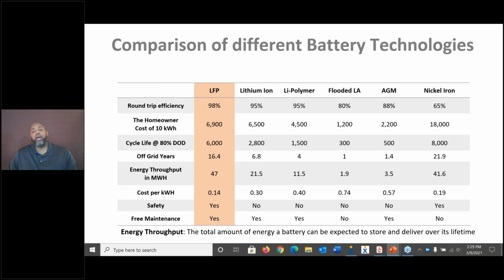If you look at the lithium phosphate chemistry, you'll notice it has basically twice the energy throughput of the other technology, and there's really no comparison with flooded lead acid. So what does that mean? The cost per kilowatt hour, when you extrapolate and do the math, the lithium phosphate technology has great cost per kilowatt hour, and that's what makes the most sense to the customer.